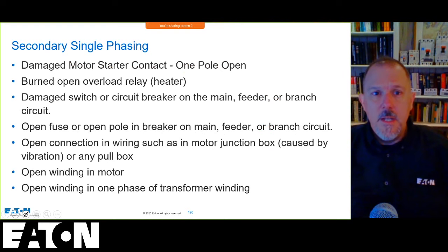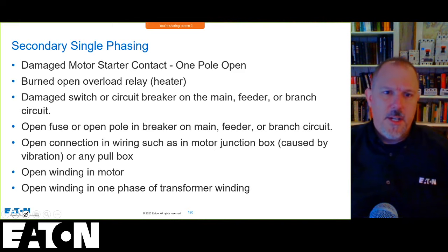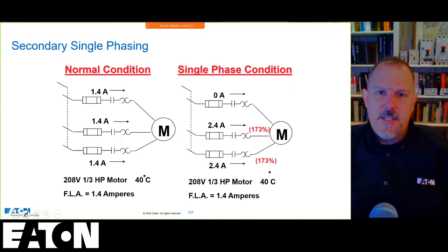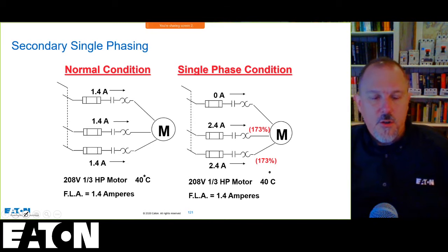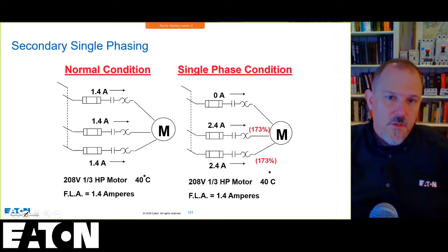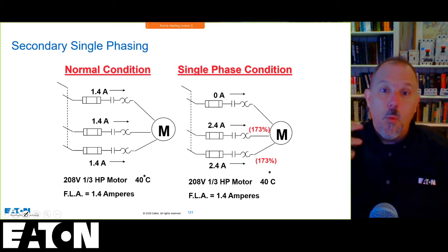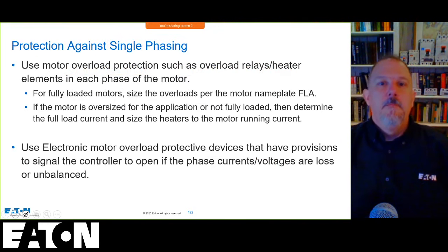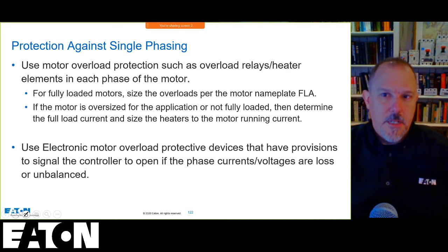That will provide protection for my equipment. If I have a secondary side, I can have damage on my motor starter contact. I can have a burned open relay, from, let's say, a heater element, or a damaged switch. One of my fuses could have opened. There are a lot of different things that can happen on the secondary side. And whenever that happens, you're going to see an overload in the other two phases when single phasing occurs on the load side, the motor side. In the other condition, I had a single phase on the source side, so I still had three phase currents going, but one of those phases was going into overload. In this case, two of the other phases go into overload. So because I'm using overload protection, relays, heater elements, things of that nature, I'm going to be protecting that motor from overloads.